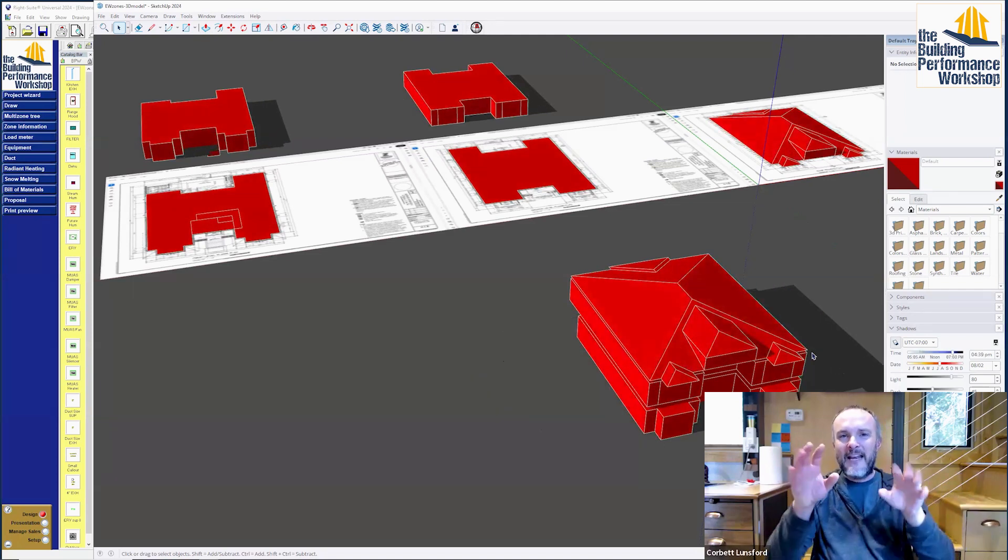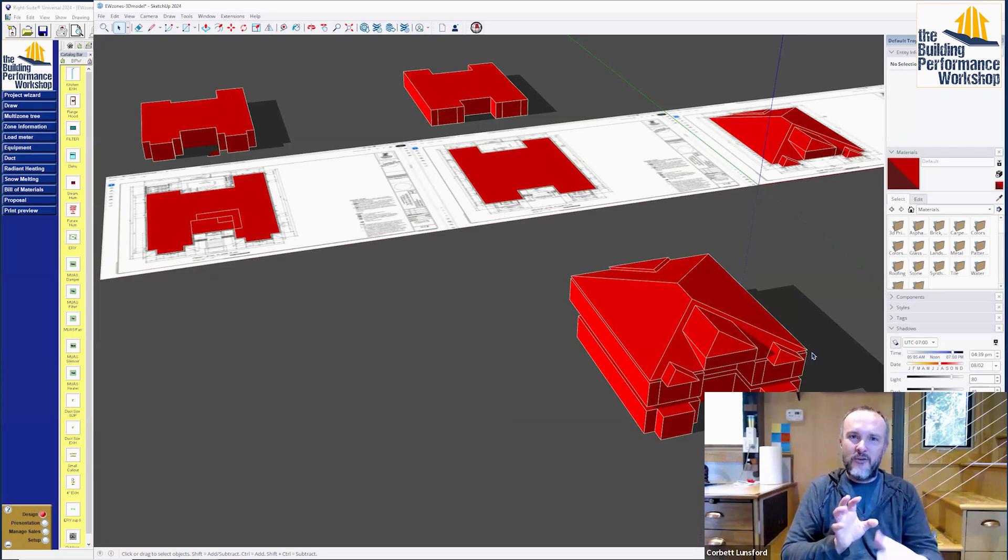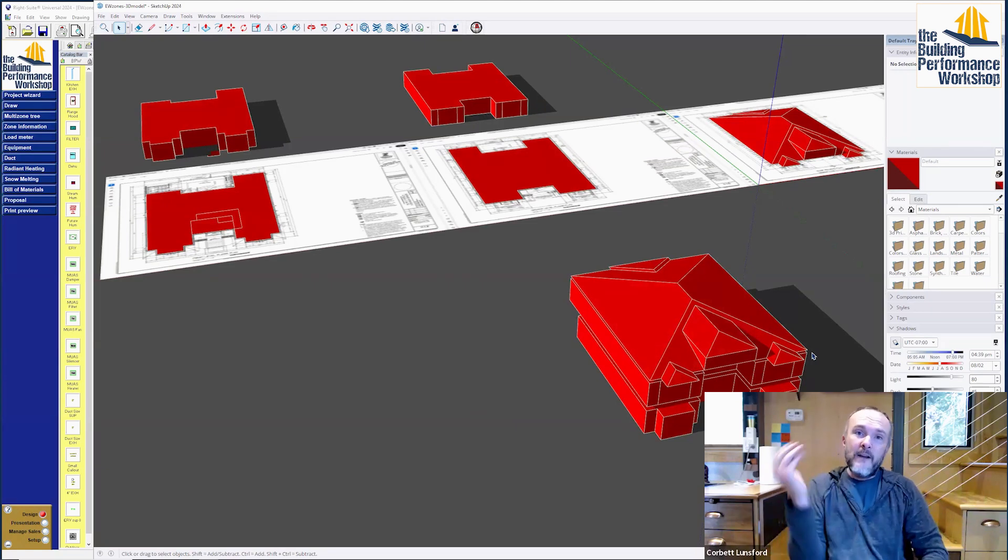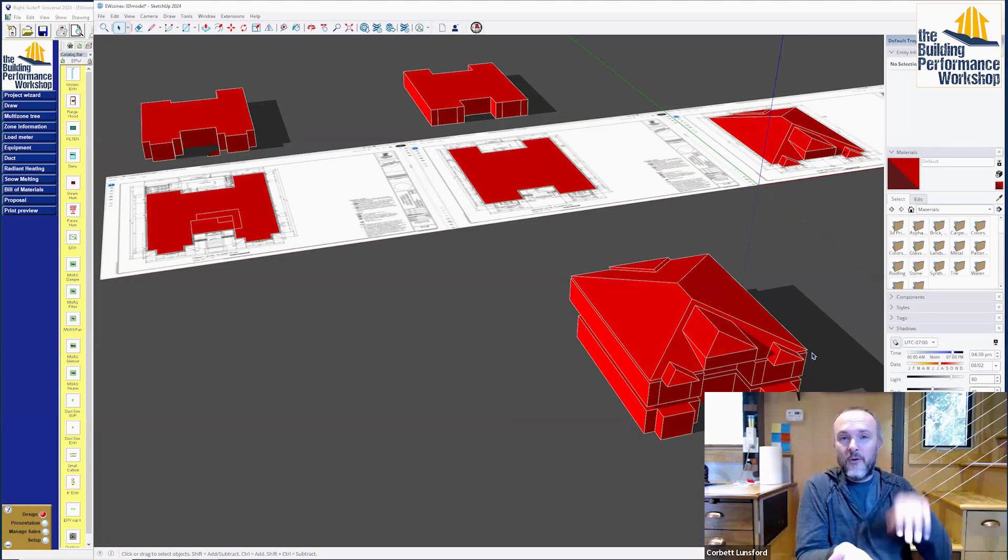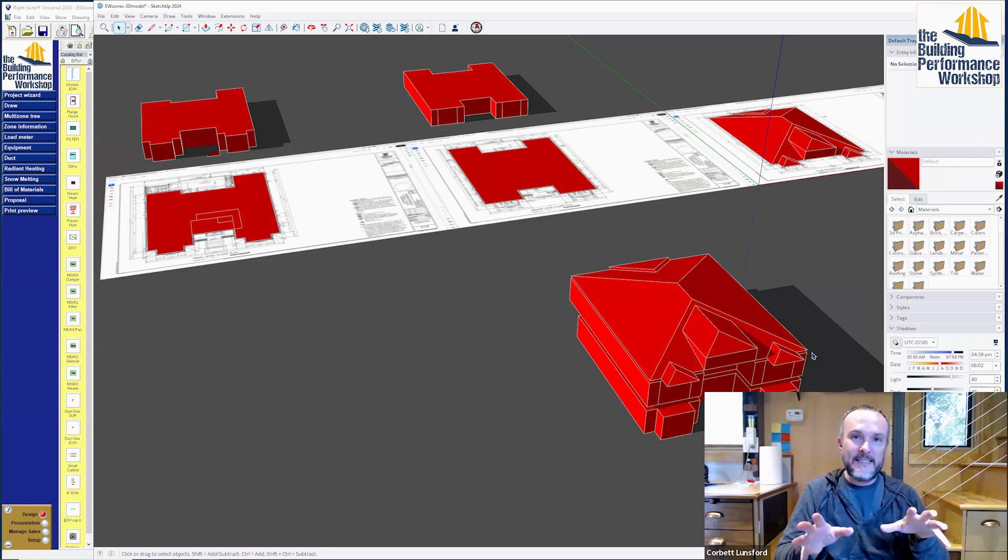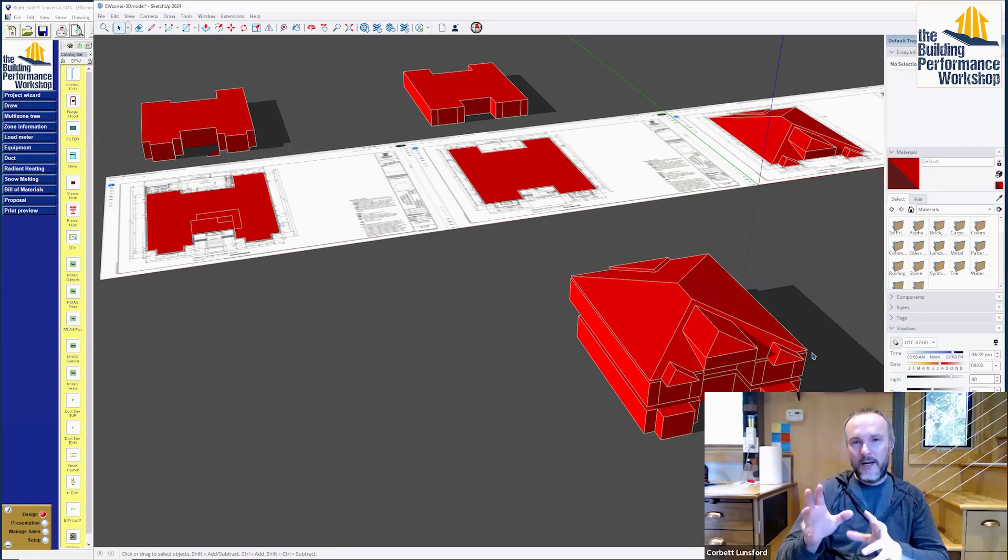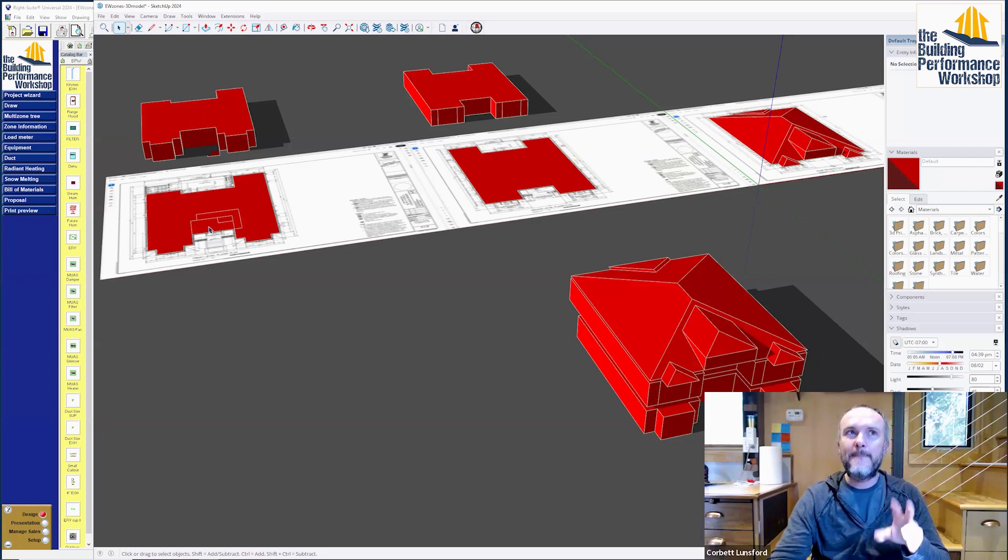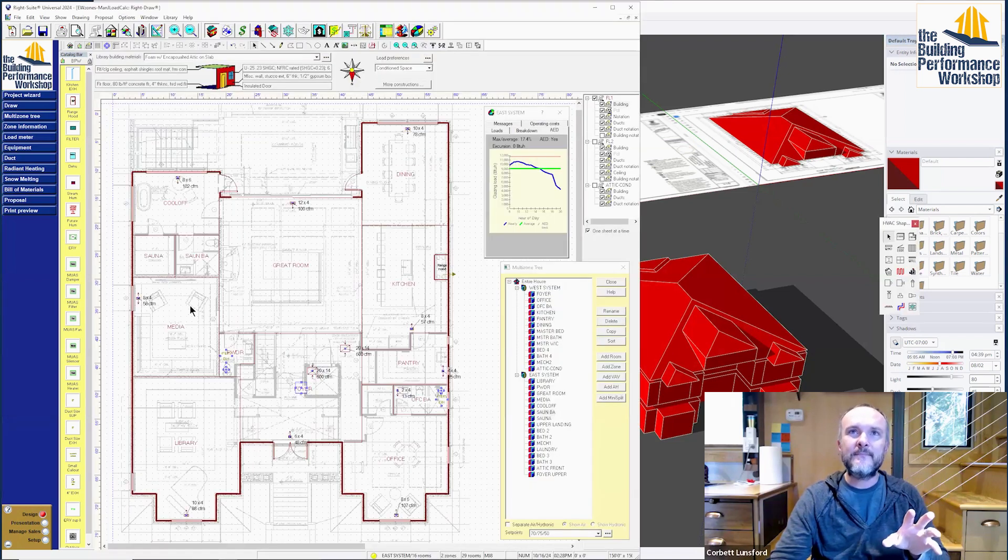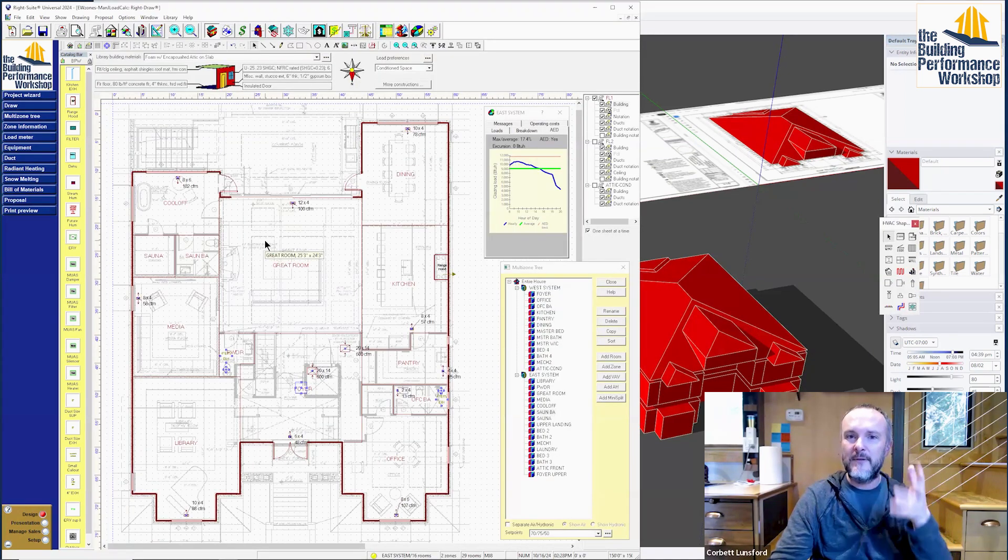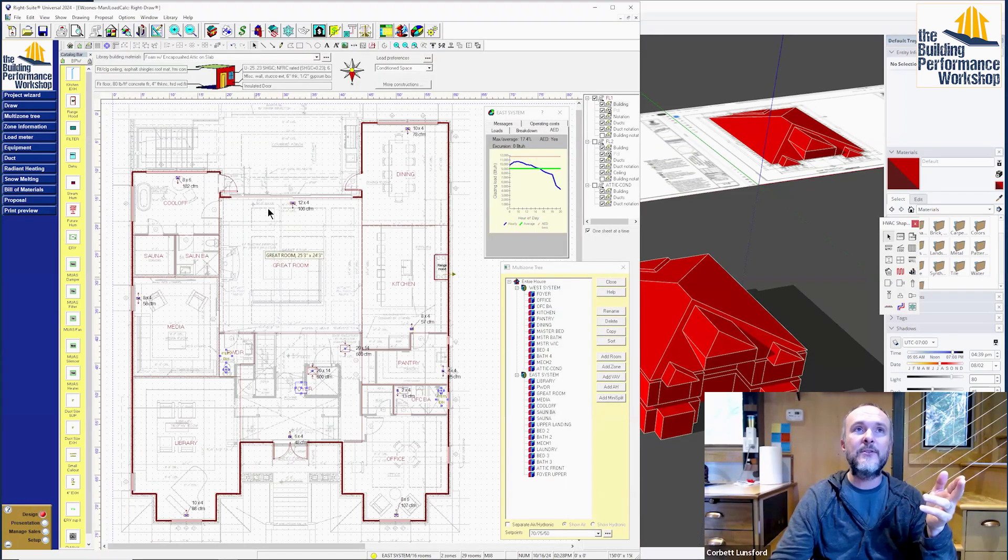That means that if we're going to zone, zoning front system and back system or bottom floor and upper floor doesn't make sense. Really, what we want to do is try and favor the east side and the west side if we possibly can. Here's what that looks like when we actually get into the design software. This is Wrightsoft that I'm using.